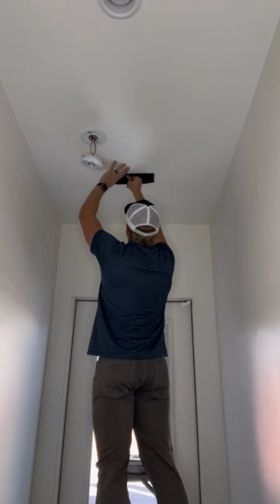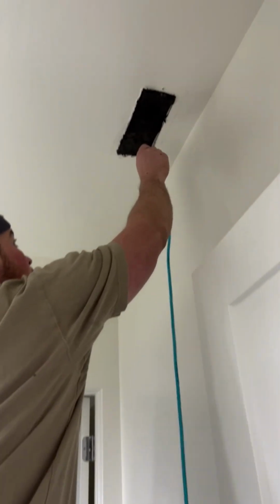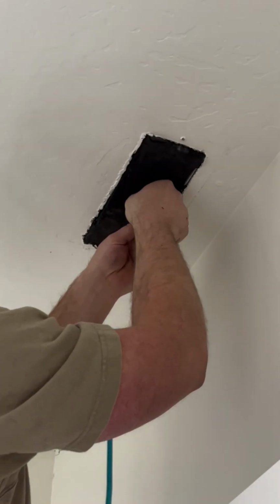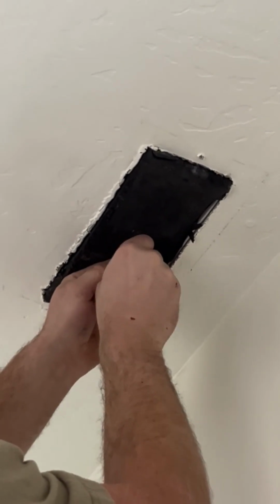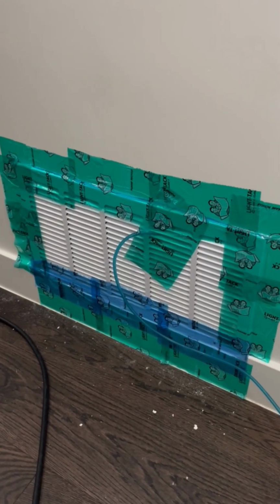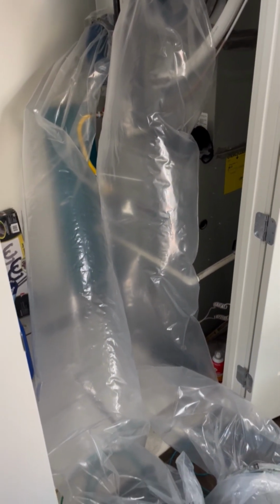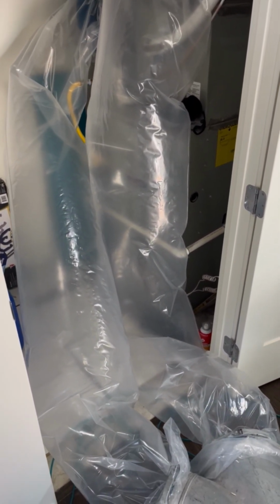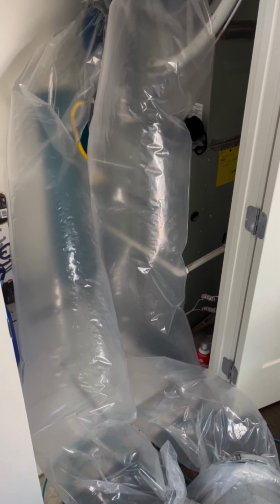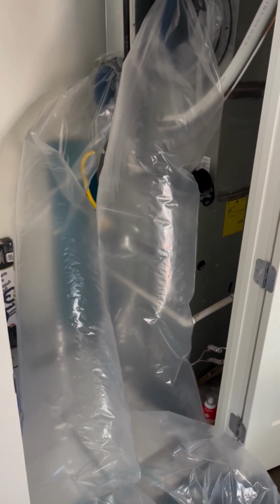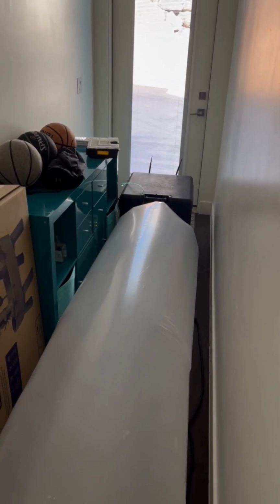After we finish plugging each of the vents, we will insert this blue tube, which is used to measure the pressure inside the ductwork. This is the supply side, and then we put one in the return side as well. Once everything's blocked off, we can perform the pre-seal pressure test to give us our baseline of how much duct leakage was in the system. You can see here that the sealant has already begun leaving the machine and heading into the ductwork, starting to patch holes.